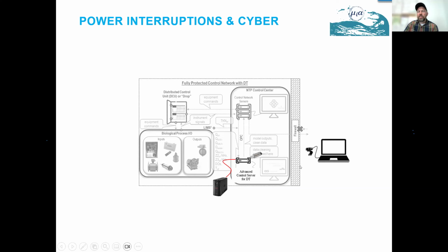Another thing that wasn't really a problem, but more of an inconvenience, was that because this digital twin doesn't sit within the cloud, it sits behind a firewall and it's on-prem, the vendors had no real way of seeing what was happening with our digital twin. When I talk about the vendors, Dynamita and CCI. So anytime we interacted with them, we had to set up a separate computer with a webcam and point the webcam at the digital twin workstation screen. We have to use flash drives to download files and then transfer those over to the computer and send to them. Like I said, not really a problem, but an inconvenience and something to be mindful of as you go through your digital twin deployment.